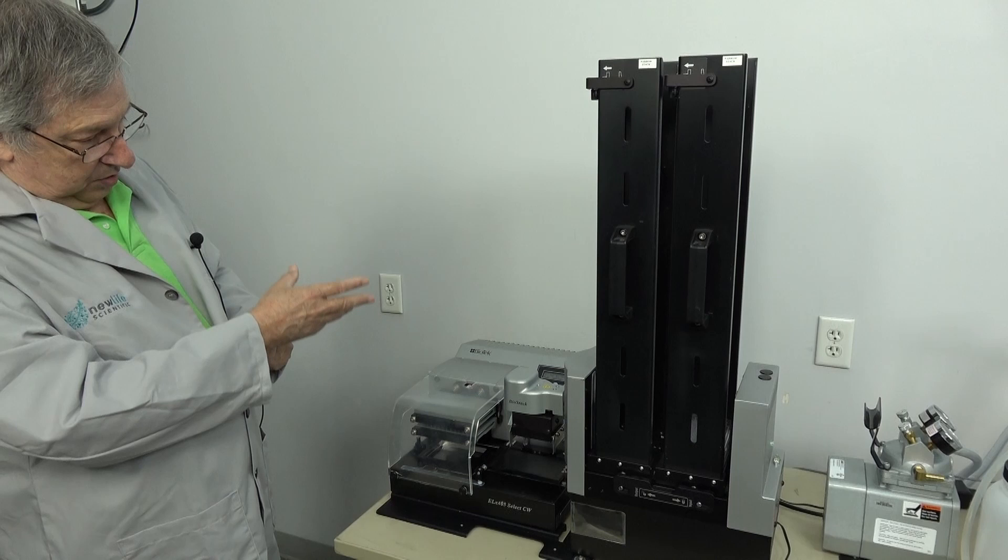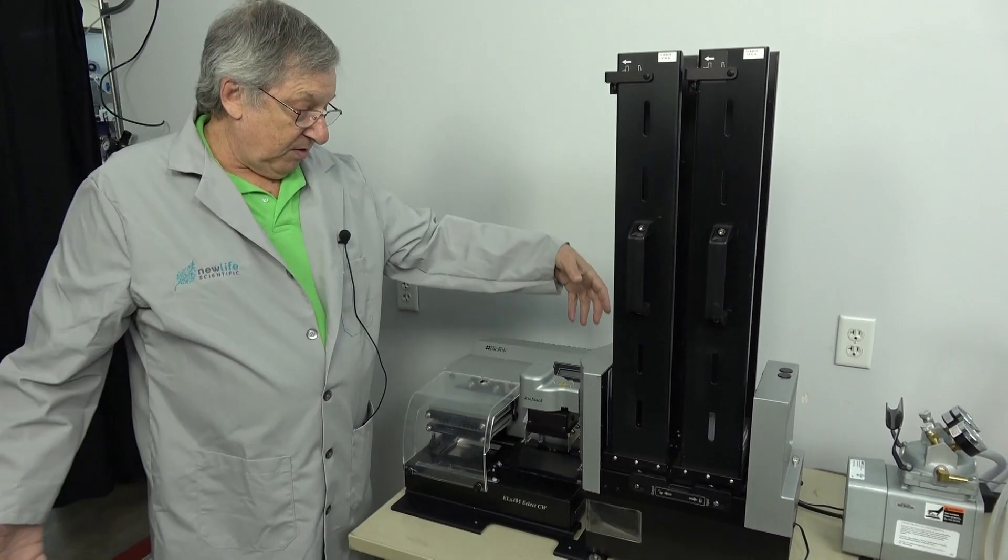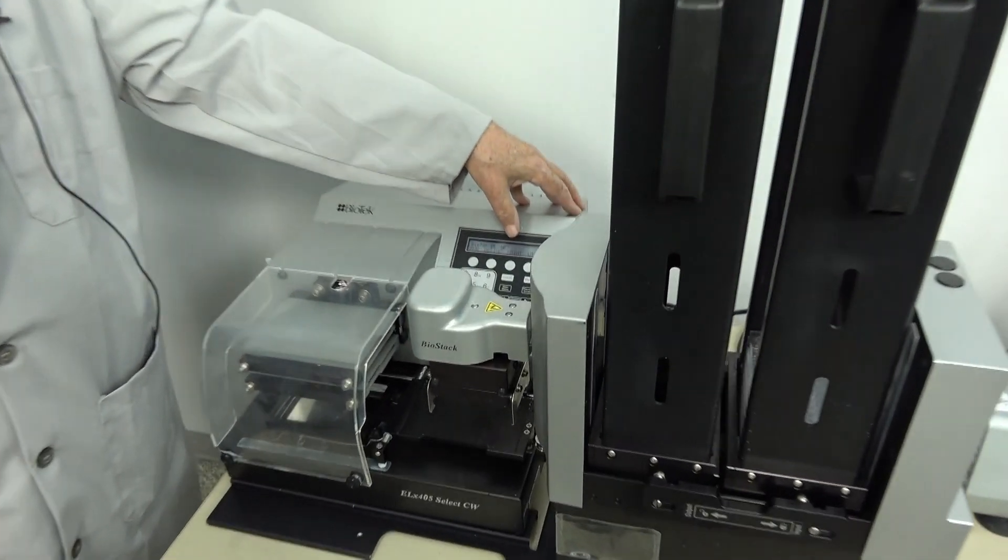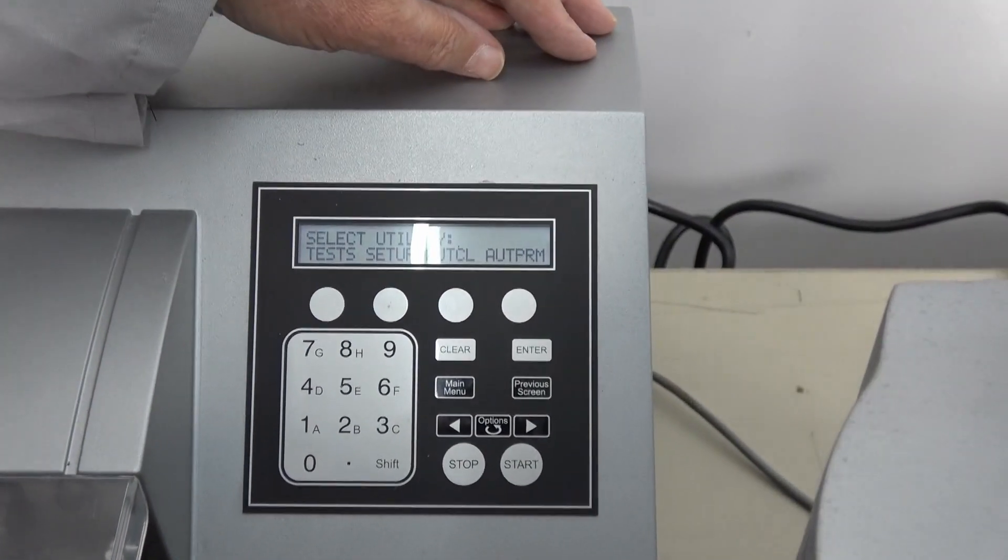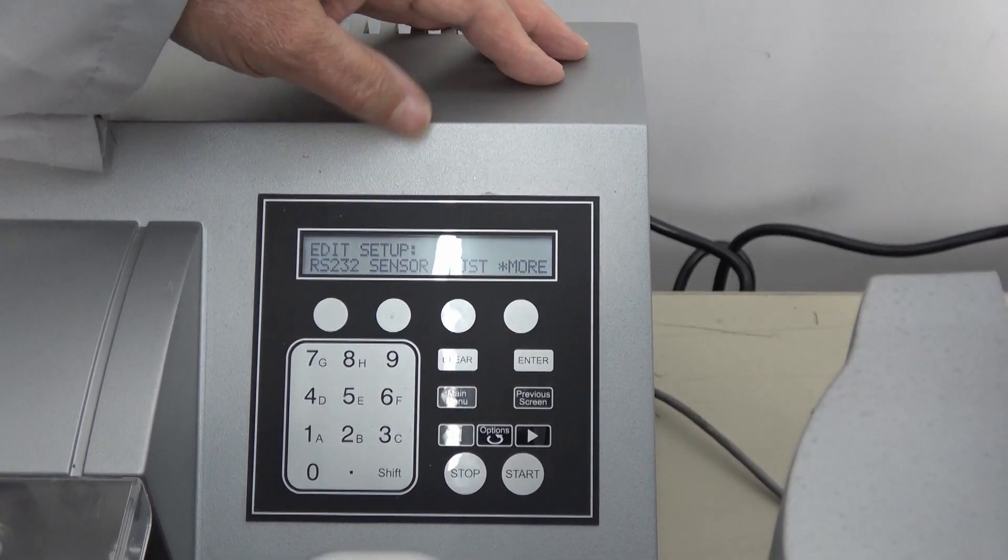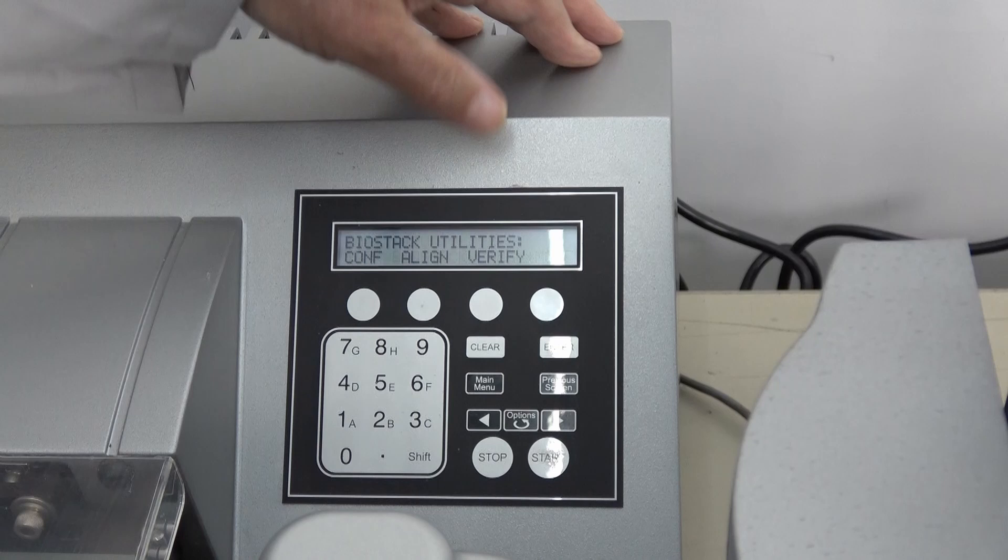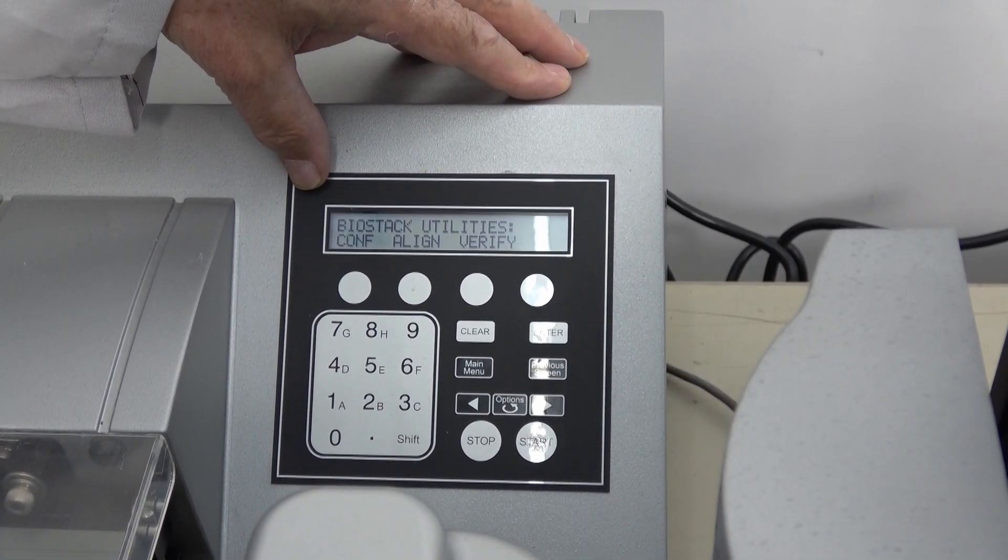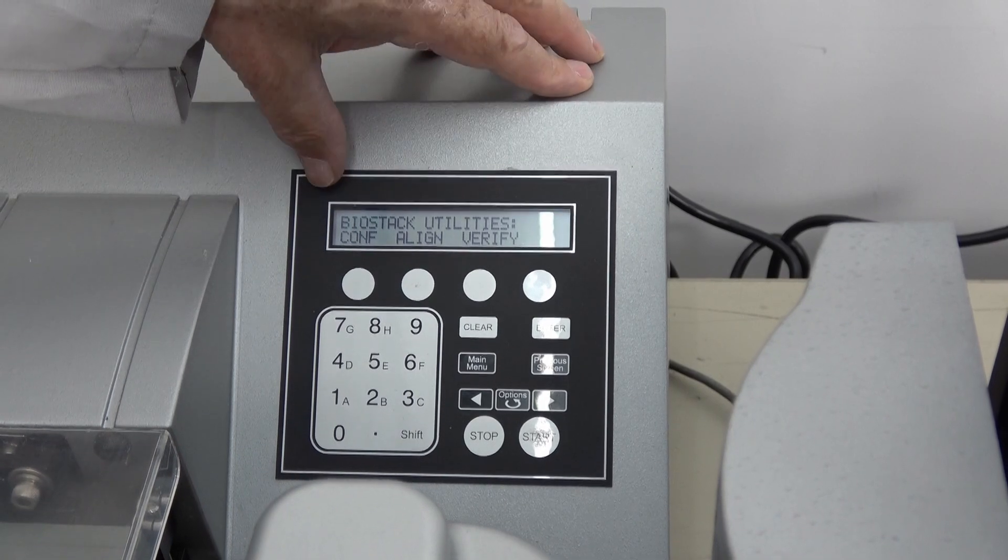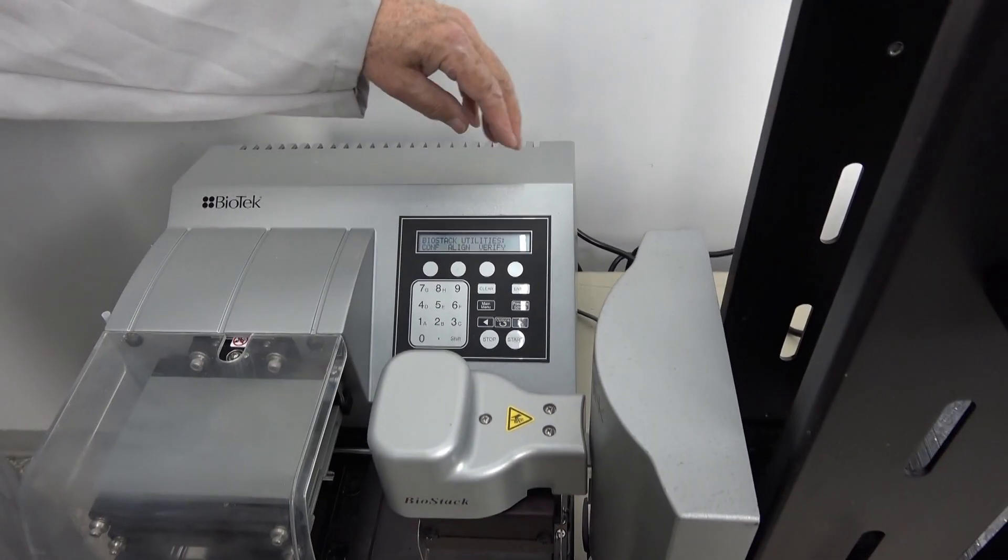There's software built into the system to help you align that. It's very easy to run. It is somewhat forgiving. That's a utility menu. Setup, more, BioStack. Those are your different things that are in that align. You can either configure it, align, or verify it. Just make sure that it sees it.